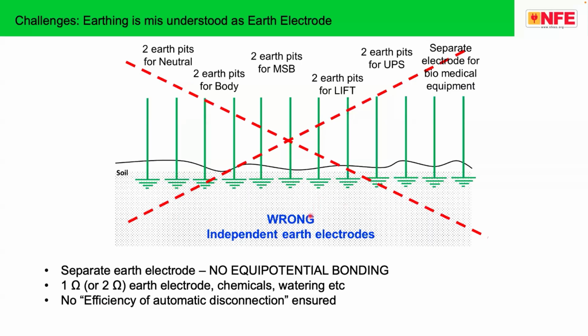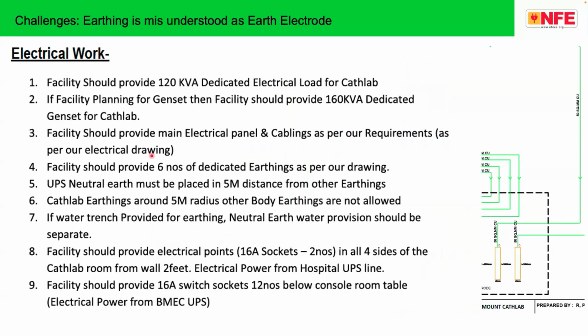So this is wrong. Biomedical equipment manufacturers are asking for separate earth pits. To some extent, this can be thought of as they are not reading, or the competency is a little bit less. But recently I saw one very interesting electrical requirement from a supplier of the cath lab, as you can see. The electrical requirement, serial number 4: facility should provide 6 numbers of dedicated earthing as per our drawing. Means dedicated earth pit. This is okay. We can educate them and we can change their mind.